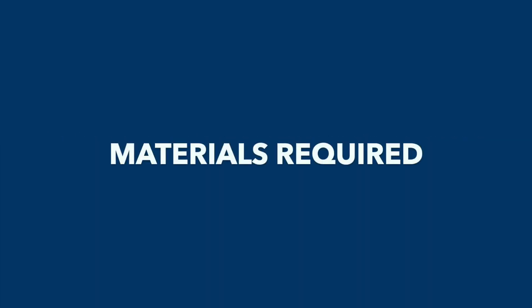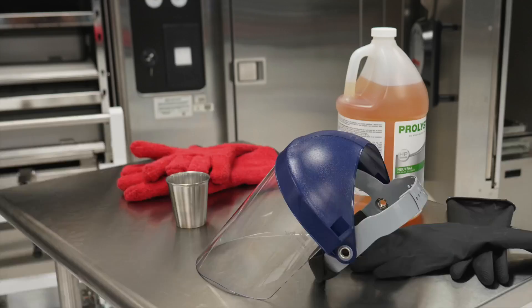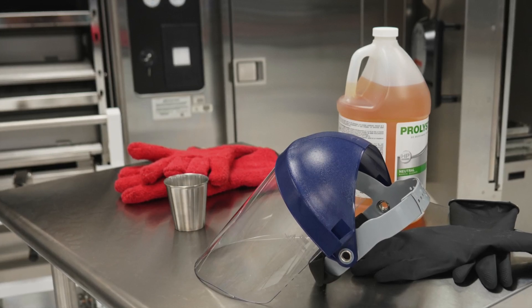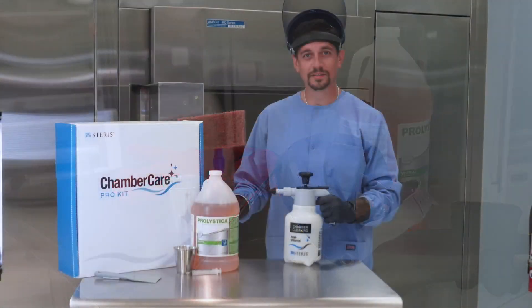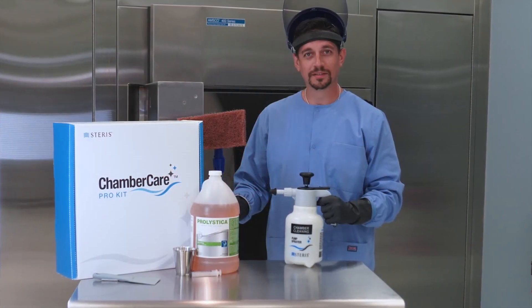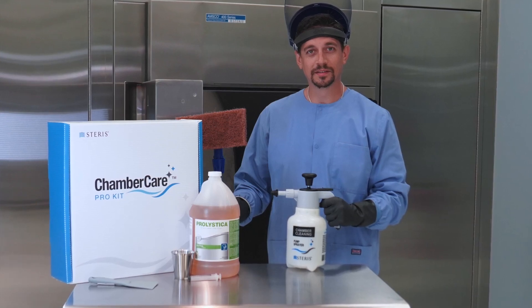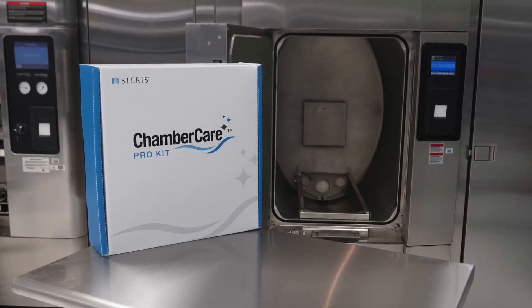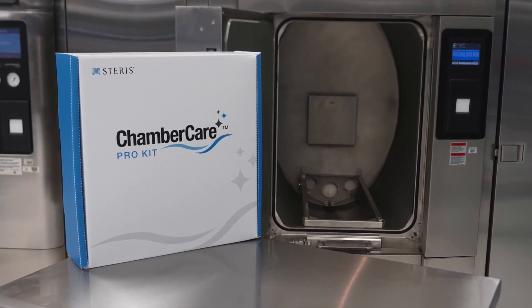Materials required. Warning: Personal Injury. Personal protective equipment including heat-resistant gloves, heavy rubber gloves, protective gown, and face shield or safety goggles are required to perform routine chamber cleaning. The Chamber Care Pro Kit contains the tools you need to perform routine sterilizer chamber cleaning following this IFU.